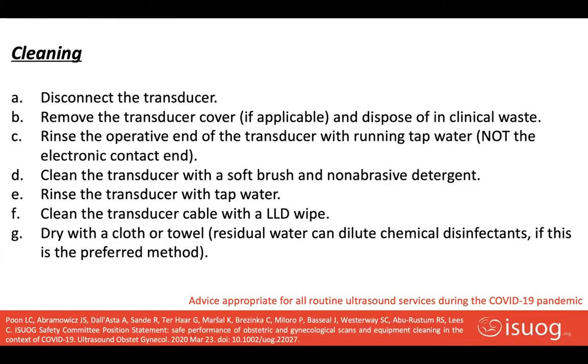Cleaning is a very, very important first step, since any remaining gel can act as a barrier to the disinfectant, thus diminishing its efficacy. The USA CDC defines cleaning as the removal of foreign material from objects, normally accomplished using water with detergents or enzymatic products. Ineffective cleaning prior to disinfection can limit the effectiveness of chemical disinfection.